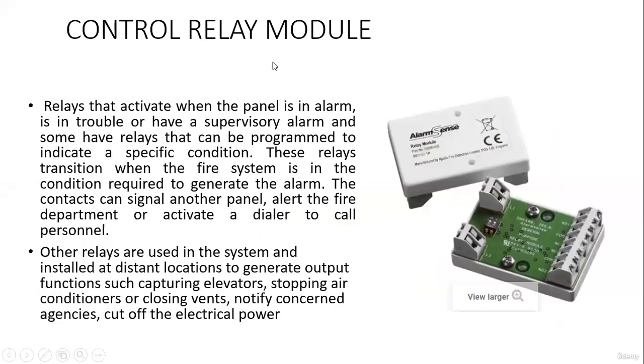Okay. And the control relay module. These are usually relays that activate when the panel is in alarm, is in trouble or has a supervisory alarm, and some have relays that can be programmed to indicate a specific condition. These relays transition when the fire system is in the condition required to generate the alarm. The contacts can signal another panel, alert the fire department, or activate a dialer to call personnel. Other relays are used in the system and installed at distant locations to generate output functions such as capturing elevators, stopping air conditioners, closing vents, notifying agencies, or cutting off the electrical power, right?